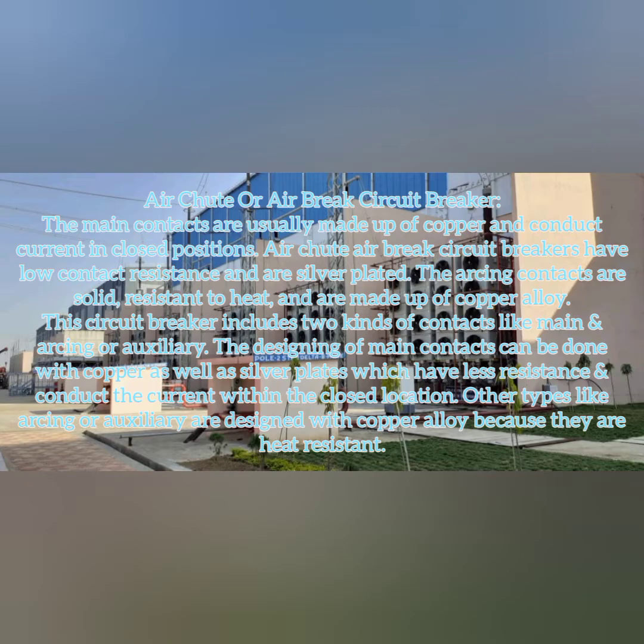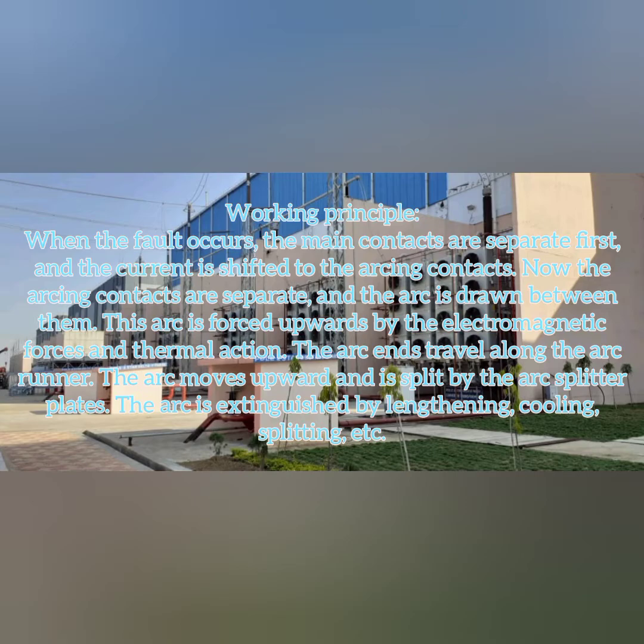The other type, arcing contacts or auxiliary contacts, are designed with a copper alloy because they should have heat resistance. The main theme is that while closing, our arcing contacts will make first and our main contacts will make next, while at the time of opening, our main contacts will open first and our arcing contacts will open next. So in this case, the arcing contacts play a vital role at the time of closing and opening of your breaker.